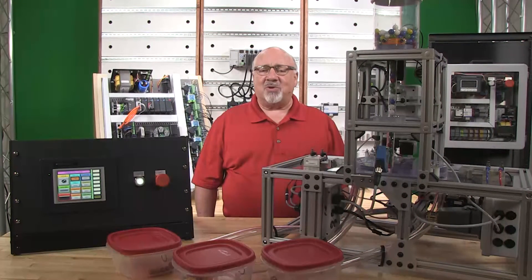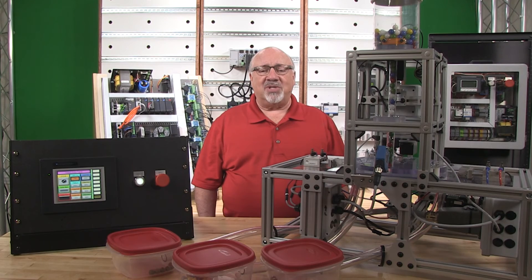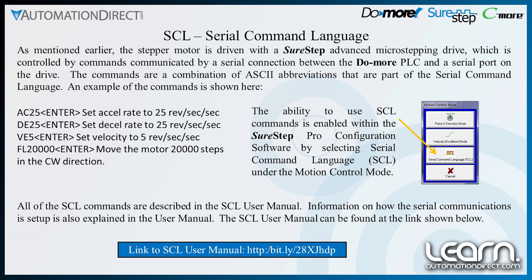The stepper motor is driven with a SureStep Advanced Micro Stepping Drive controlled by commands communicated via a serial connection between the DoMore PLC and the serial port on the drive. The commands are a combination of ASCII abbreviations that are part of the serial command language. For example: AC25 sets the acceleration rate to 25 revs per second per second; DE25 sets the deceleration rate to 25 revs per second per second; VE5 sets the velocity to 5 revs per second; and FL 20,000 is feed to length, which moves the motor 20,000 steps in the clockwise direction. All SCL commands are described in the SCL user manual, available at the link shown here.